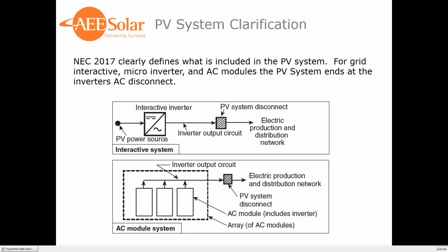All right, so, PV system clarification. The NEC 2017 clearly defines what is included in the PV system. For grid interactive, microinverter, and AC modules, the PV system ends at the inverter's AC disconnect. They gave us diagrams, straight from the NEC 2017, in the beginning of the code article that clearly define what is included in the PV system. So for the interactive system, we have the PV source, let me get the laser pointer, we have the PV source here that goes to the grid interactive inverter and the inverter output circuit to the PV disconnect. So this section right here is all that is included in the PV system. Same thing with AC modules, or microinverter type systems, up to the first disconnect.